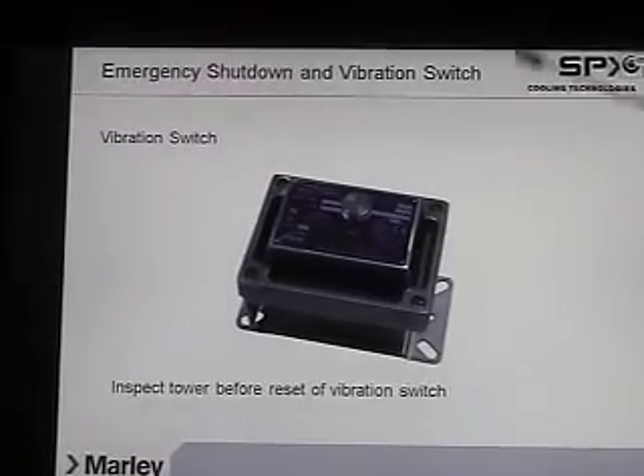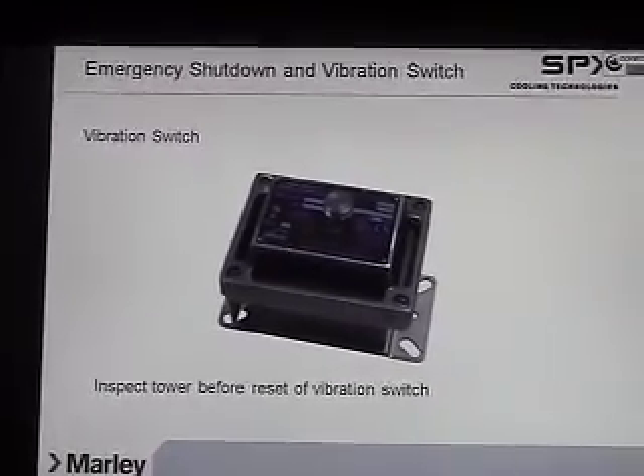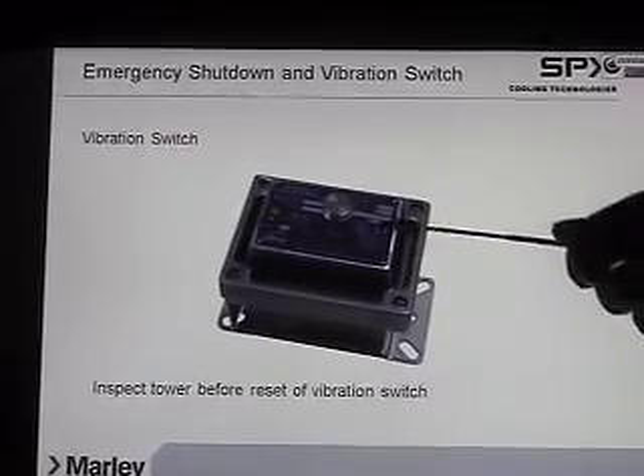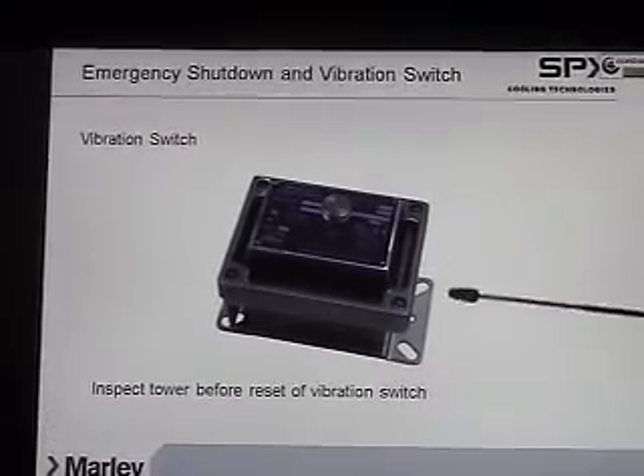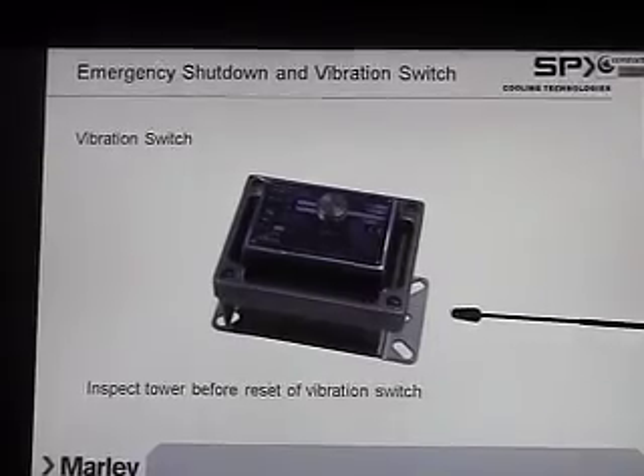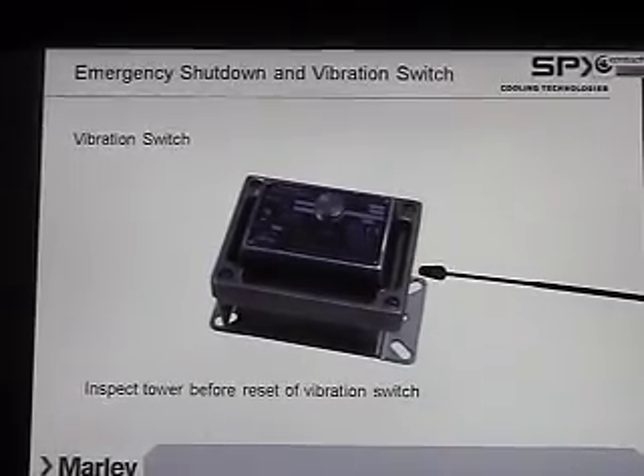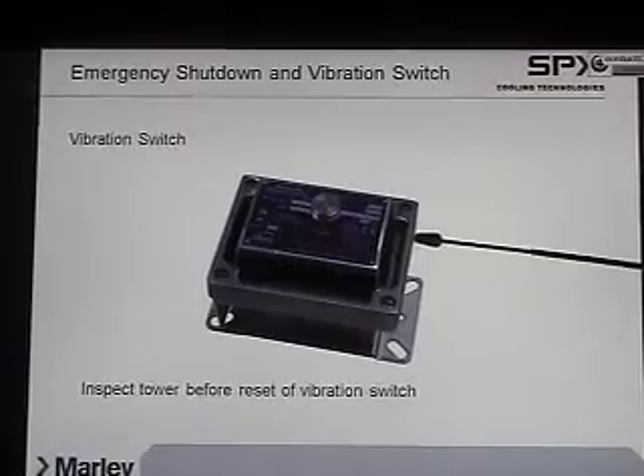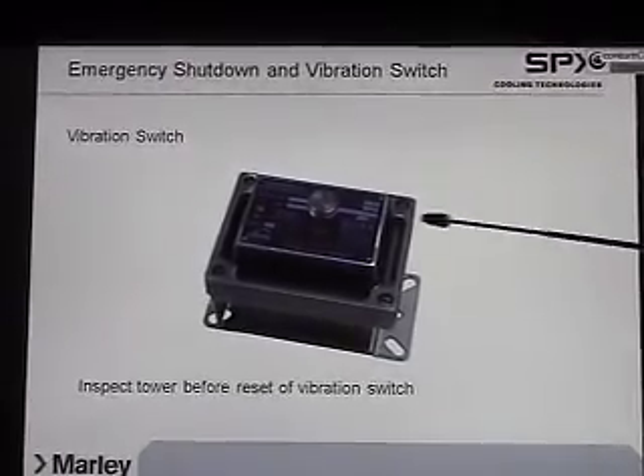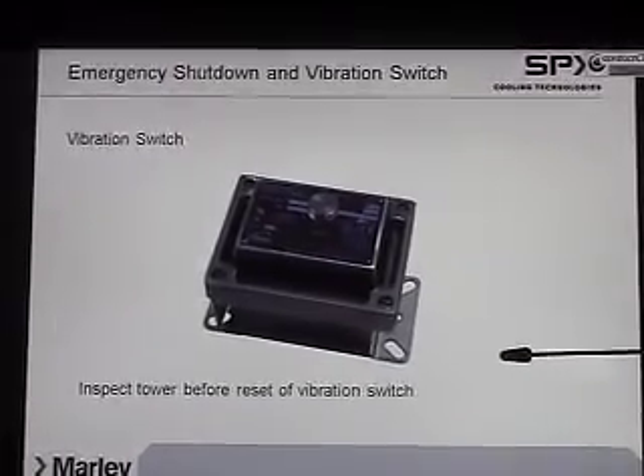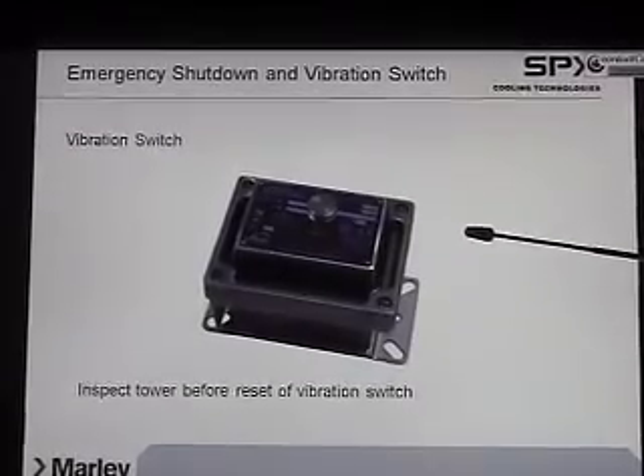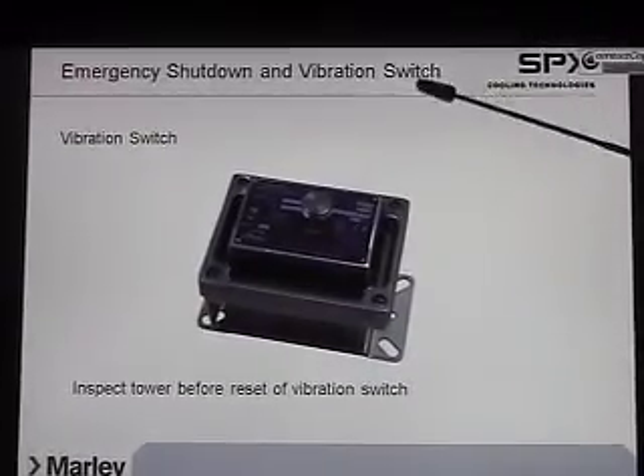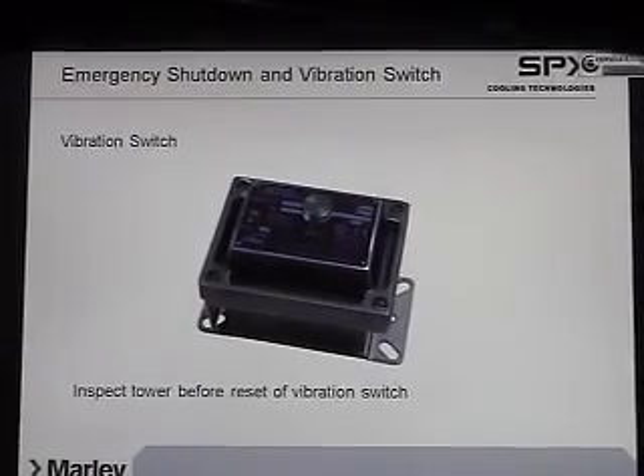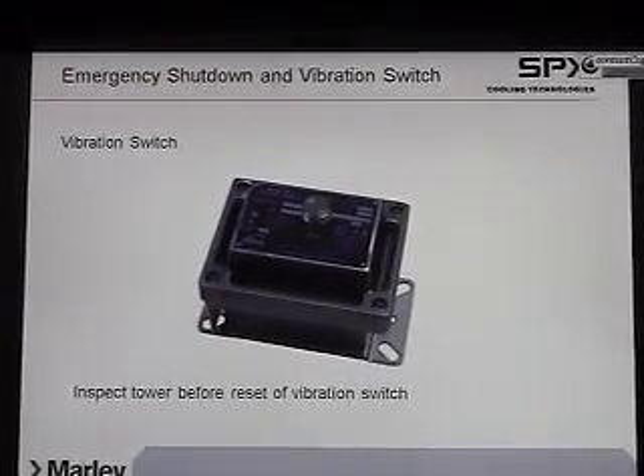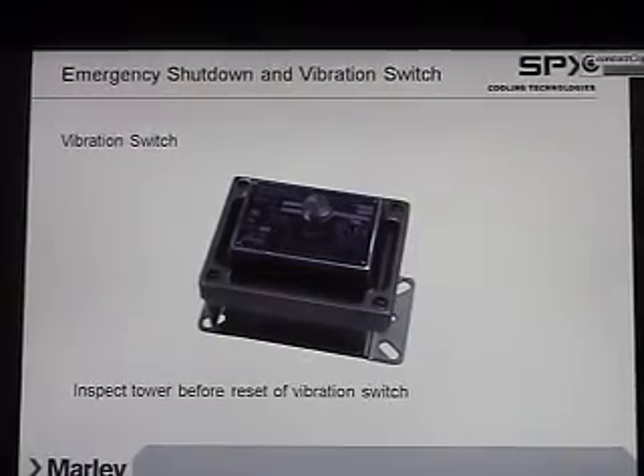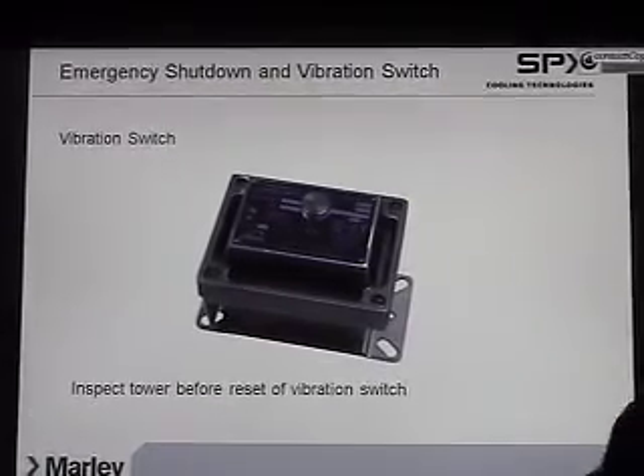This is the vibration switch. It's up on the cooling tower right next to the motor. First you would make sure everything's okay. Sometimes they just trip because of a little excess vibration. They're designed to not trip on startup. After you check to make sure everything is okay, you just push this button to restart it. And if you want to test it, all you have to do is just kind of bang on the lid right there by it, and it'll trip it. That's how we tested it at startup.